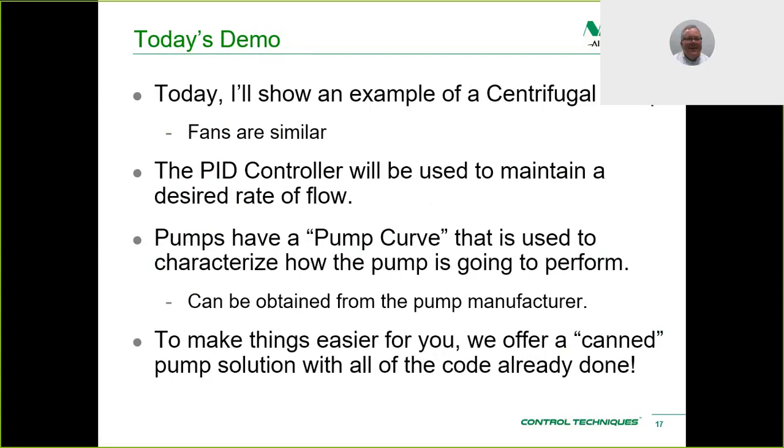Normally, in pumps and fans, we don't set the minimum speed to zero. Certainly in the case of a pump, pumps don't like to be run dry, so we normally would set the speed to a non-zero value, and if you wanted to get technical about it, you'd refer to that pump curve that I just referred to, to find out what that point is.